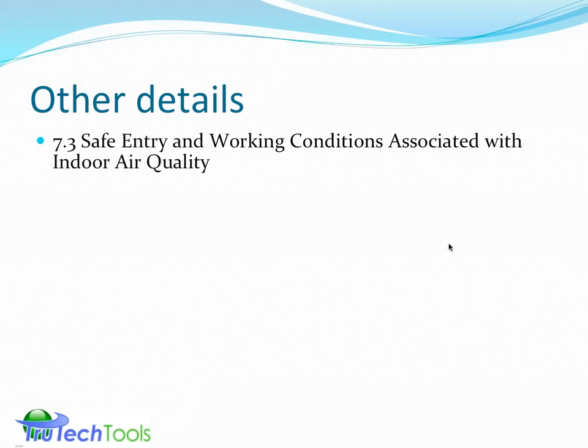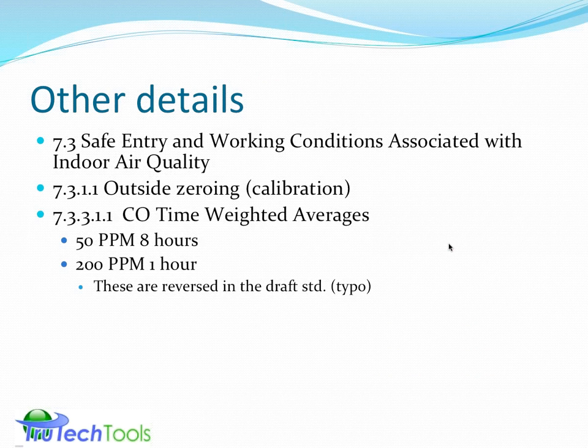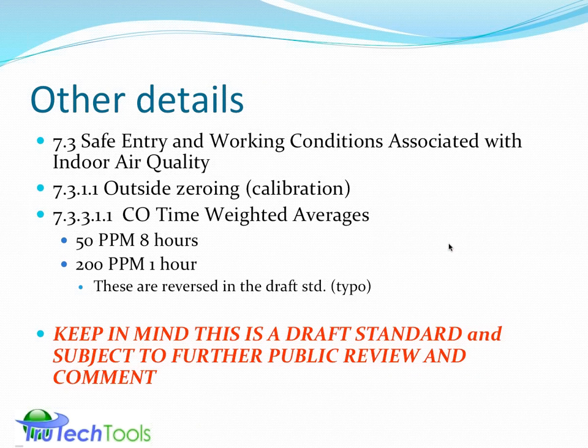So some other details. 7.3 talks about safe entry and working conditions associated with indoor air quality. Outside zeroing or calibration in 7.3.1.1. And then talking about time-weighted averages for CO. The draft standard does have these reversed, which I believe is a typo for these time-weighted averages. The other impact here is that the time-weighted averages require some means in your personal CO monitor for monitoring and recording these time-weighted averages, because CO is a cumulative poison, and for reporting and alerting to these levels, which would put you in another class of product.